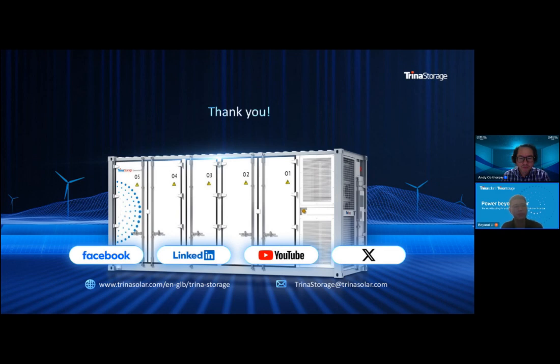Some of the system integrators may use two container units combined with one single PCS, but this could give rise to a lot of issues, especially the loop current and the non-uniformity or discrepancy of performance between the battery containers. So this is somehow not suggested for such solutions. That's why I would advocate the idea of even larger capacity battery cells. Thank you.